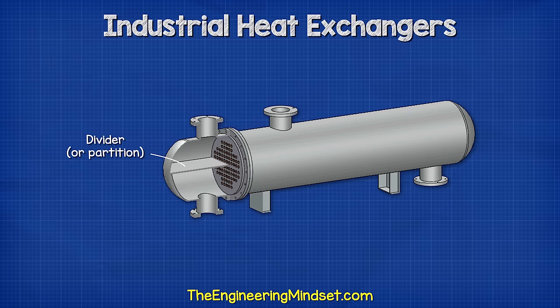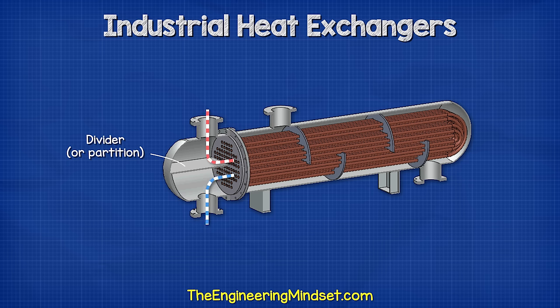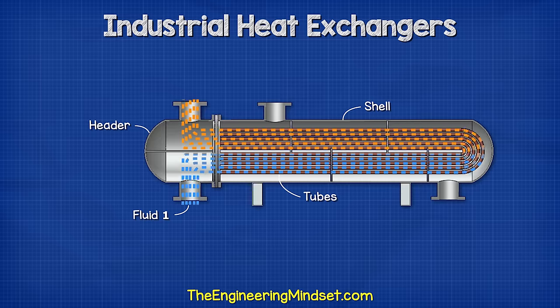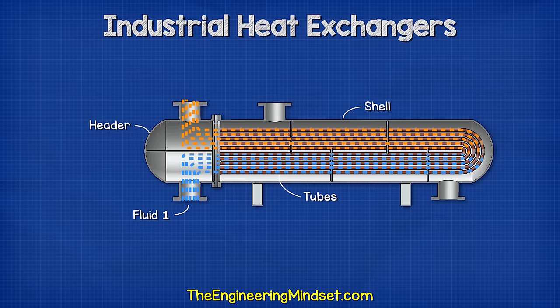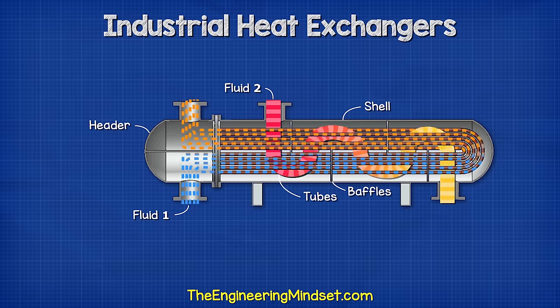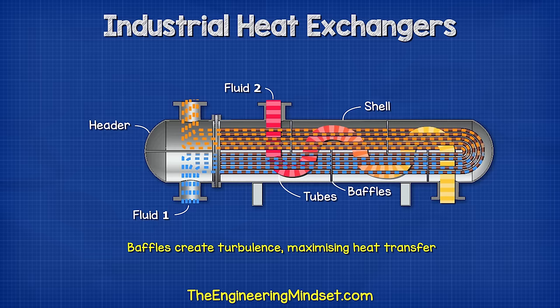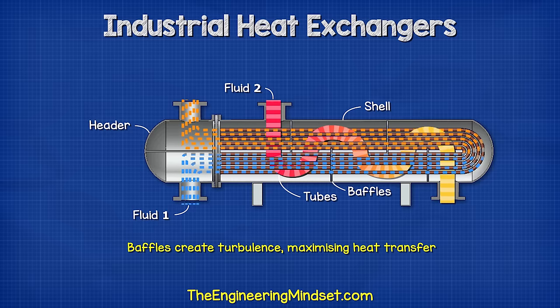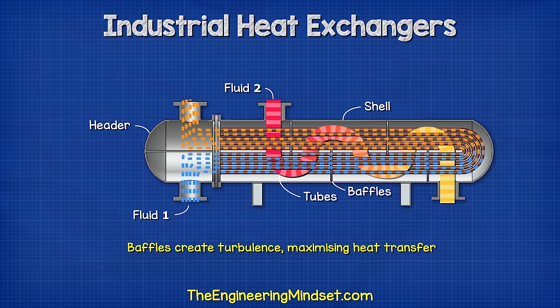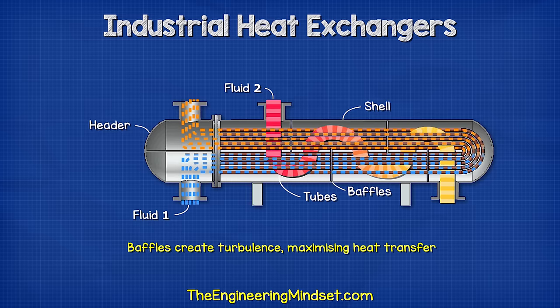Inside the header is a sheet of metal known as the divider or partition. This separates the tube ends, enabling the fluid to flow into and then out of the heat exchanger tubes. Fluid 1 flows through the header, into and around the tubes, then back to the header. Fluid 2 enters the shell and surrounds the outside of the tubes. The baffles partially block the flow, forcing the fluid to turn multiple times. This creates a turbulent flow and ensures that fluid 2 mixes with itself, which ensures maximum heat transfer.